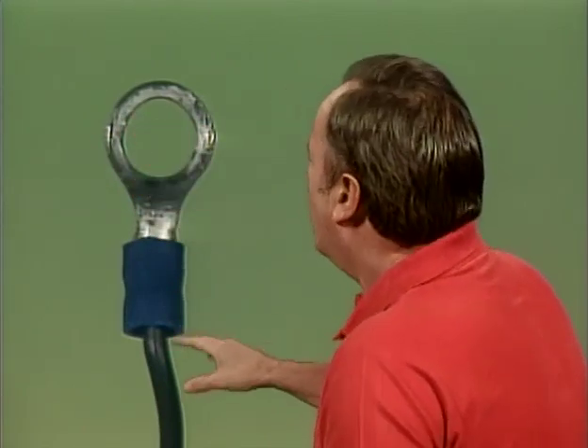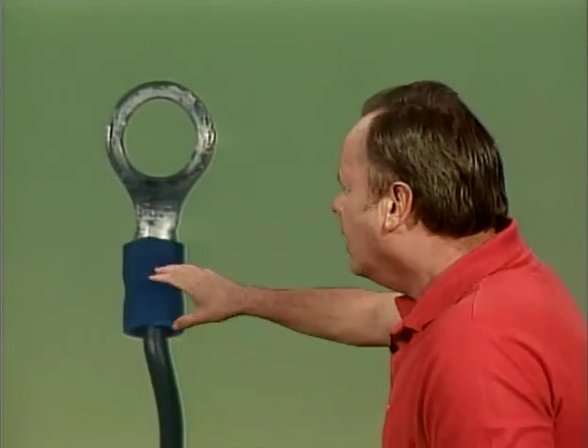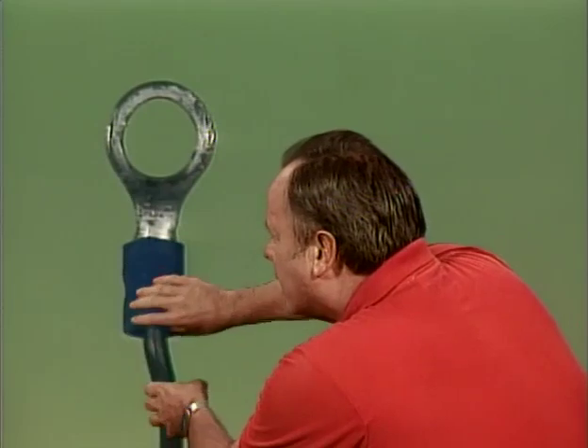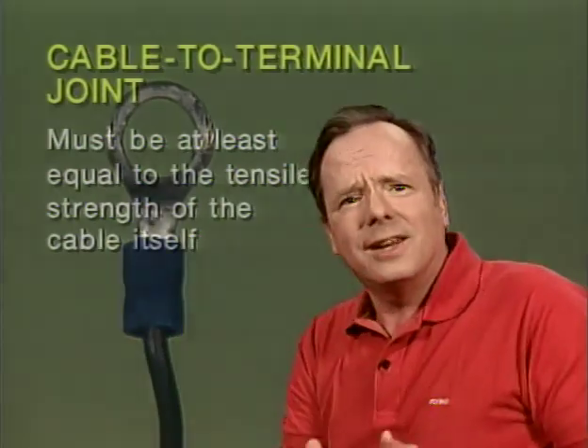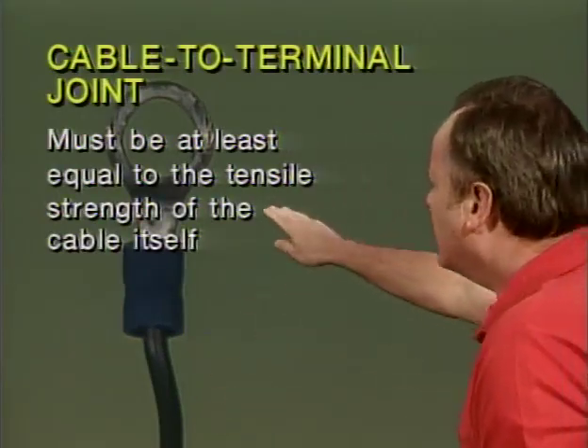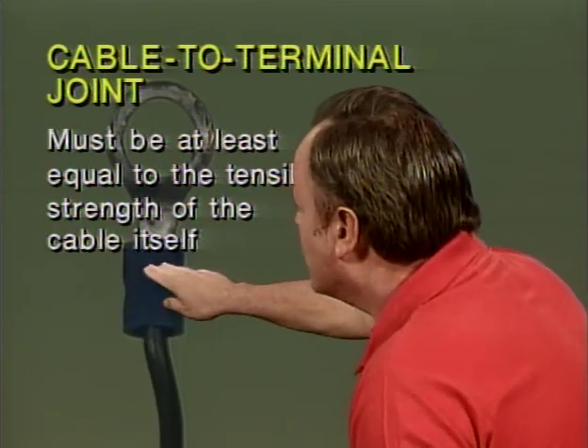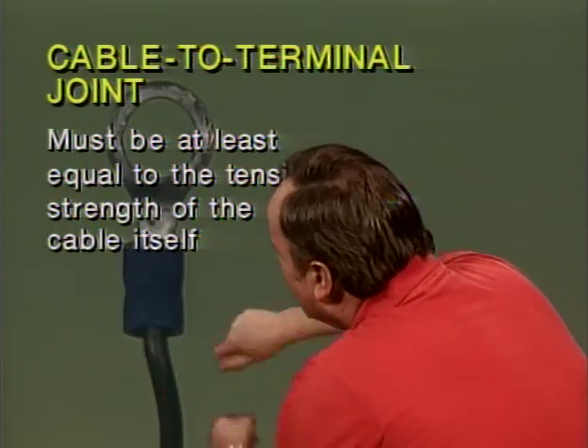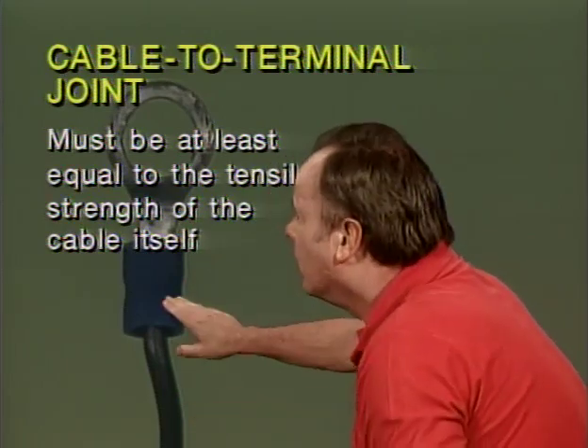like this. Now, when you're attaching a terminal like this to the end of an electric cable or a wire, the strength of this joint here, the cable to terminal joint, must be at least equal to the tensile strength of the cable or wire itself, because you don't want the joint to fail. If anything's going to fail, you want it to be the cable or the wire.